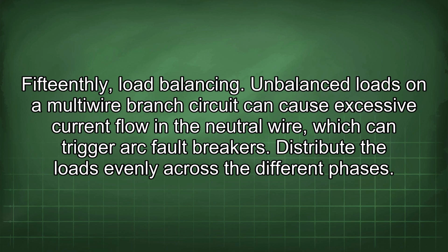Fifteenthly, load balancing. Unbalanced loads on a multi-wire branch circuit can cause excessive current flow in the neutral wire, which can trigger arc fault breakers. Distribute the loads evenly across the different phases.